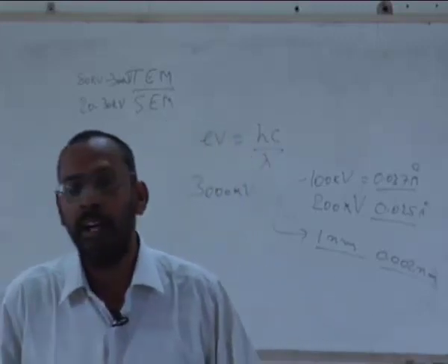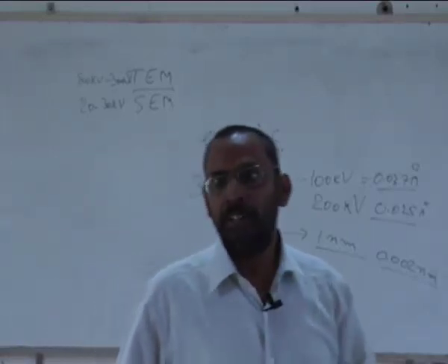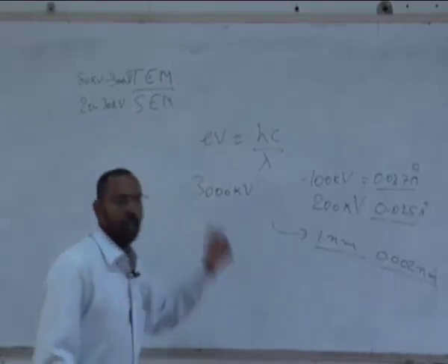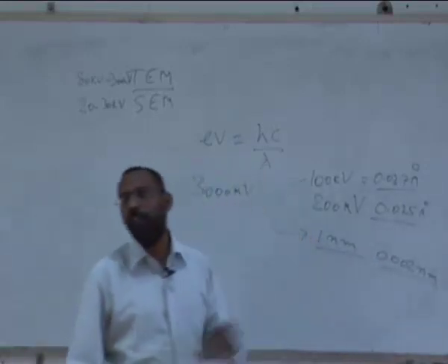And even magnetic lenses have their own aberrations, chromatic aberrations, spherical aberrations, all these are there. And it is those aberrations which limit the resolution, and you are not able to achieve the resolution which the small lambda is able to offer. The only way to improve is, instead of going to very large voltages, which will give you much smaller lambdas, because already even with this lambda you are not able to achieve very high resolution.